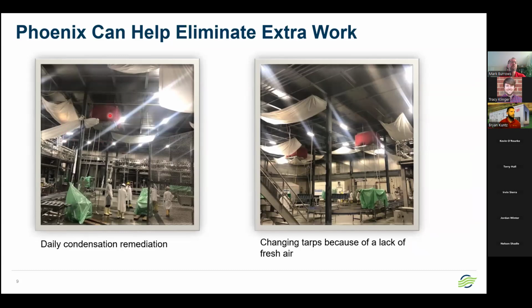The other thing going on, they put a red sock, for lack of better words, around their diffuser, rather than really addressing the root cause issue, which in this case happened to be high face velocity off these diffusers, wicking moisture from the diffuser heads and over open product. So they put the sock, the old term, what is it? Put a sock in it. They took that in a literal sense, and they did that for their short-term solution, which is probably fine. But given the nature of where these are located, I'm sure that they are not replacing them very often. You're probably just creating another avenue for bacteria to grow and then expel outwards. Another thing that just shouldn't be needed.